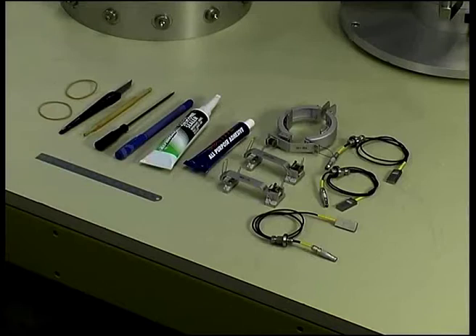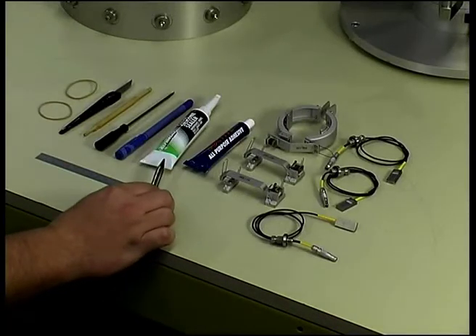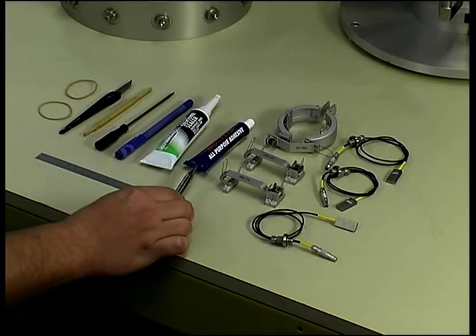All purpose contact adhesive or silicone sealant. If pins are to be used we locate the devices with silicone sealant. In this demonstration we have a very stiff sample therefore we will be using the contact adhesive to locate the transducers.